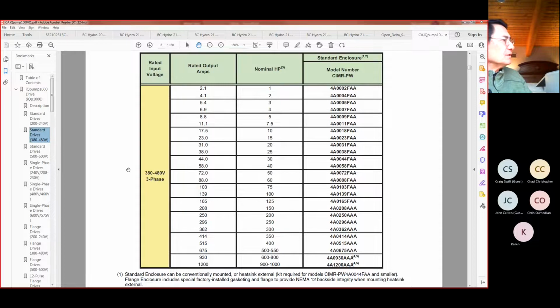In the case of a true single phase input, the derate is much more severe. Again, taking the 75 horsepower application, which you can see in the part number here, is a 103 amp drive that corresponds to the column for rated output amps. So a 4A, 4 being 480 volt, a 0103 is a 103 amp drive. That's the 75 horsepower three-phase application.